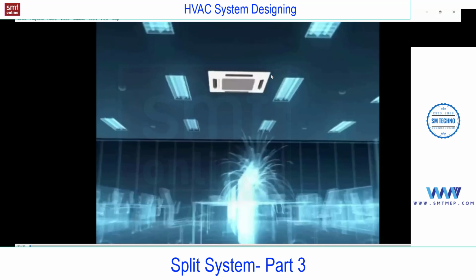You see, this is the front panel of the cassette. Only this portion is visible. The complete assembly is above the false ceiling, and this is the false ceiling level. This middle portion is for suction, and these are all for supply. In most models, you'll find four-side supply. In Daikin, you'll find the round flow, so they are offering an opening here also. Compared with the high wall, we have the advantage of better distribution. In cassette we have four outlets, but in the Daikin model they are offering the round 360, with an opening here also. In the video, you'll find this.